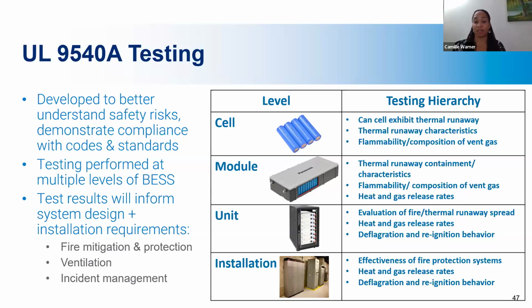Again, this is a destructive test to make sure fire doesn't spread. It's done in stages, starting at the cell level, then moving all the way up to the installation. It's just a performance test. If you're stopped at the cell or module level, you need to take the data, redesign, and begin again. This testing, UL 9540A, requires one cell propagation test, and the results will help inform the fire protection engineer to make sure they have the right protection measures for that specific system.